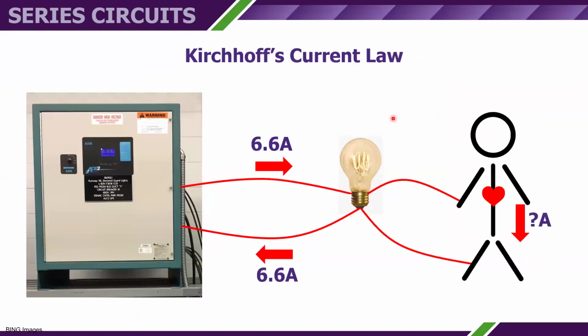Kirchhoff's current law. We want to make sure that we understand that current takes every available path back to the source. 6.6 amps leaves the regulator, 6.6 amps must return to that regulator. It's not looking to go to ground. It will take whatever path, or however many paths possible, to get back to that regulator. If you become part of that path, it will flow through you. We need to make sure that we do not become part of the series lighting circuit.